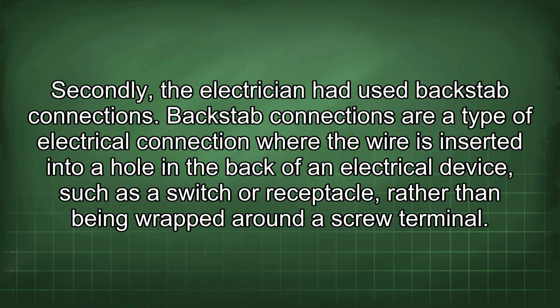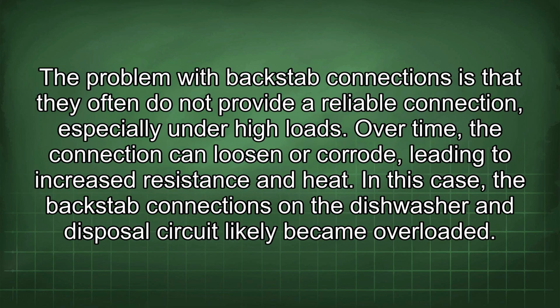Secondly, the electrician had used backstab connections. Backstab connections are a type of electrical connection where the wire is inserted into a hole in the back of an electrical device, such as a switch or receptacle, rather than being wrapped around a screw terminal. The problem with backstab connections is that they often do not provide a reliable connection, especially under high loads. Over time, the connection can loosen or corrode, leading to increased resistance and heat.